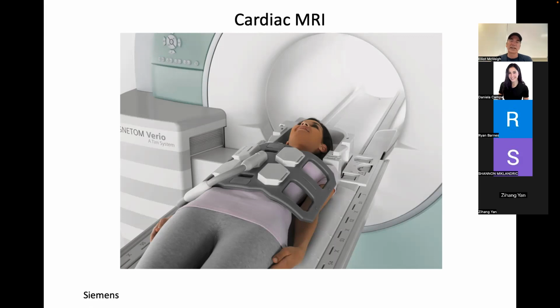And also designing coils like this one, where you have a massive coil array around the patient's chest, and you might have 6 coils on the top here, 6 coils on the bottom, so that it's really lighting up the appropriate spot. As we'll see, this coil is going to be receiving radio frequency signals from the patient that are on the orders of millivolts, microvolts. So it's a very small signal coming out of the patient, but if you put coils close enough, you can hear it, you can listen for that.